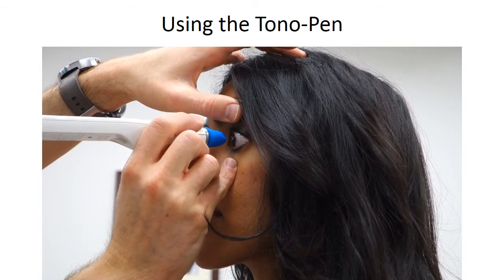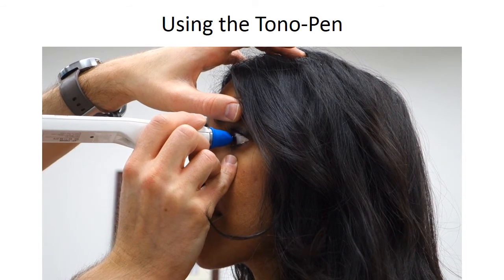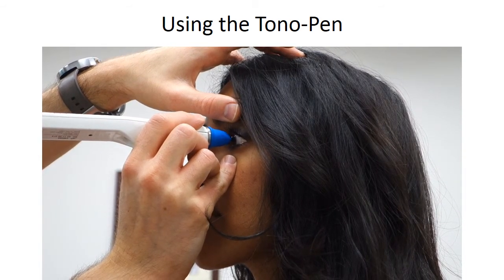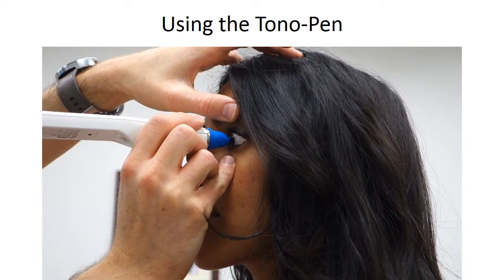After the eye drops have been placed, instruct the patient to look straight ahead and open their eyes widely. Hold the Tono-Pen as you would a pencil. Depress the operator's button once, and make sure that the 2 dashed lines are indicated. Use the tip of the Tono-Pen to lightly tap the cornea several times in rapid succession. You need only touch lightly. You do not need to press hard. Only brief contact with the cornea is required each time, and you will hear a beep every time that happens.